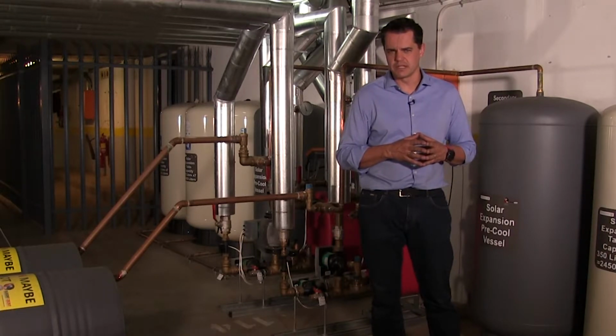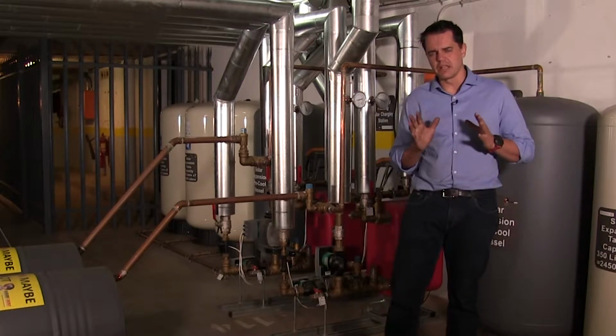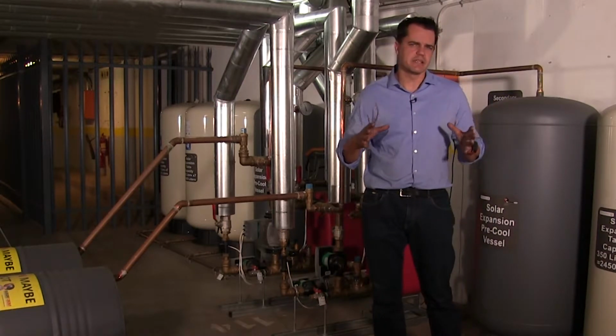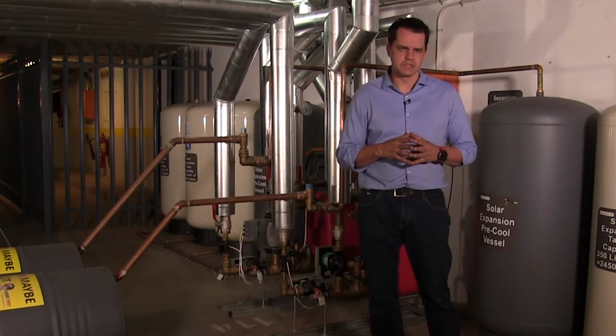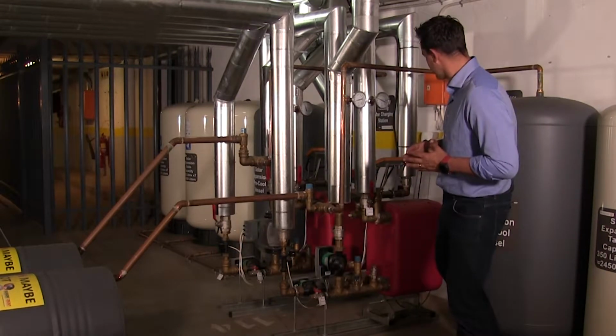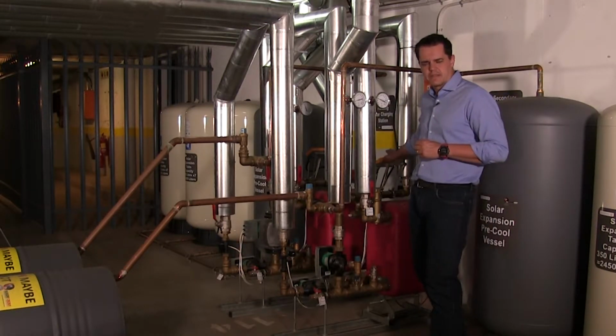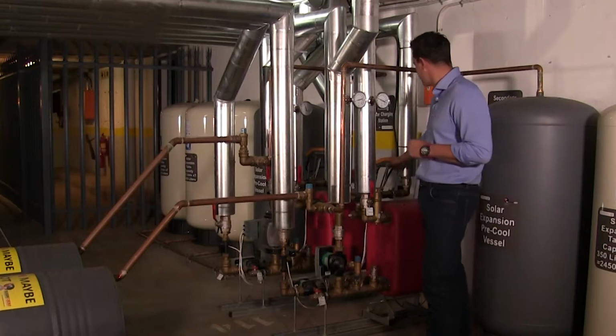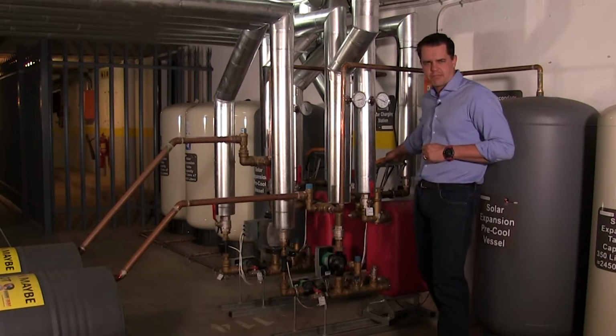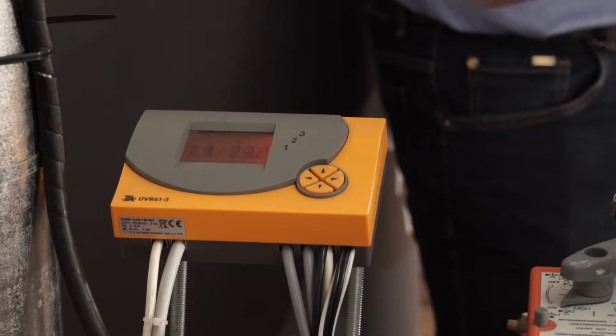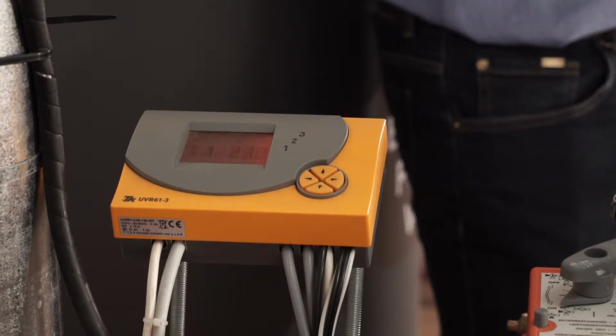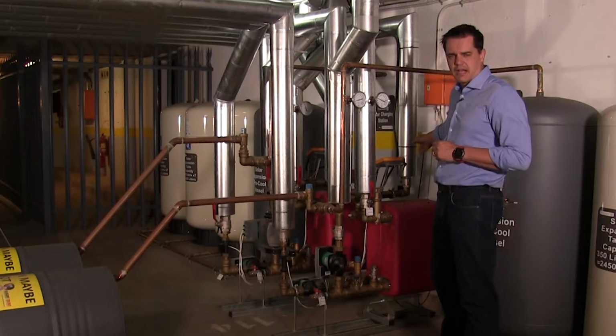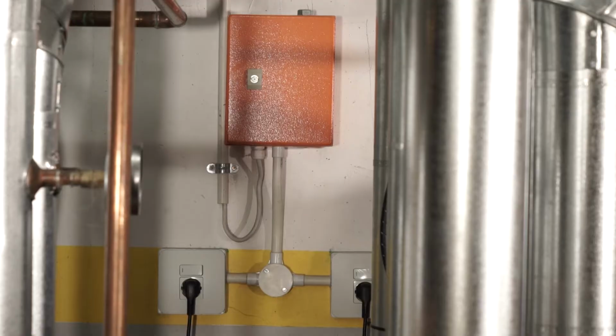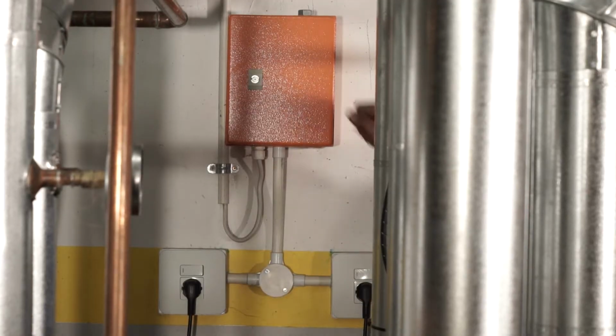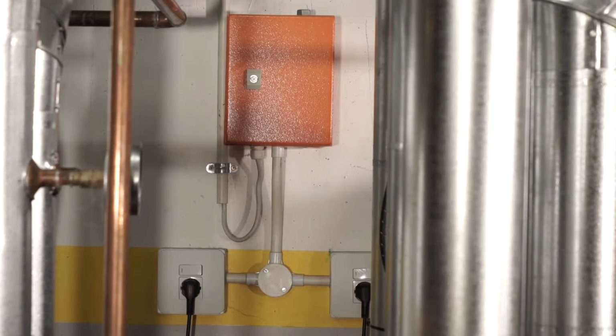So first of all, and the main key section: is there electrical power to the system? The way that you'll identify that is our controller, the Technische Alternative controller at the back, should always have a display. If there's no power or no display on that controller, there is in fact an electrical isolator switch at the back. Check that that is switched on, and also the trip switch at the top.